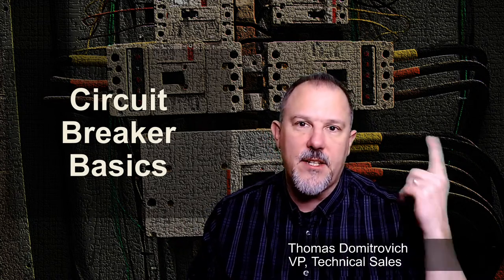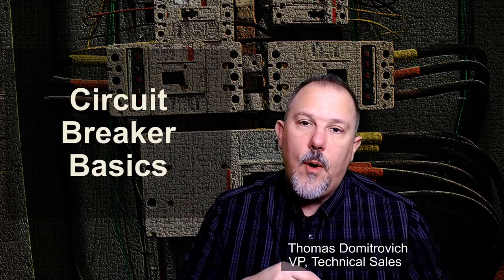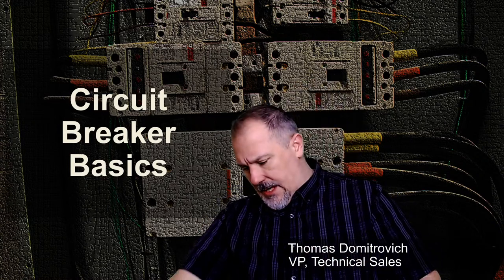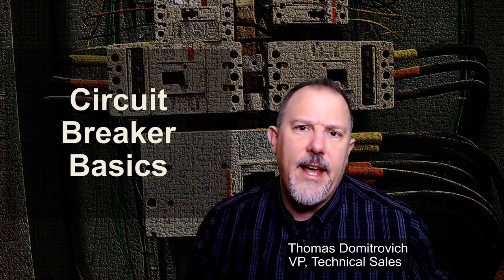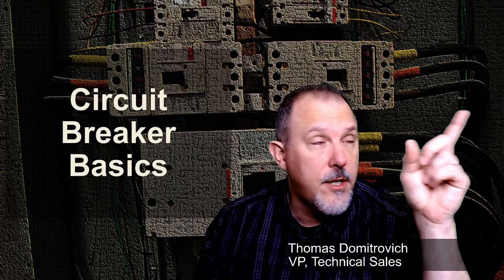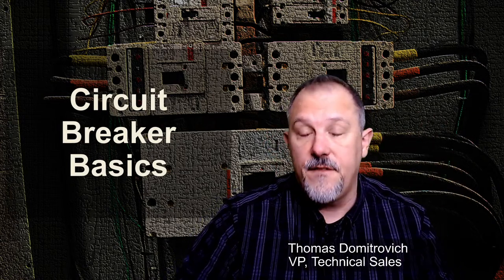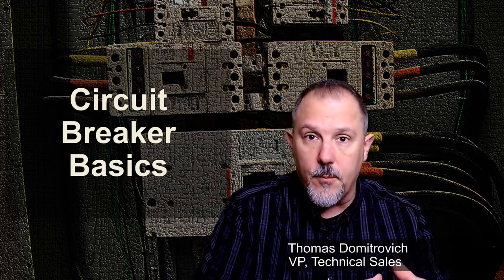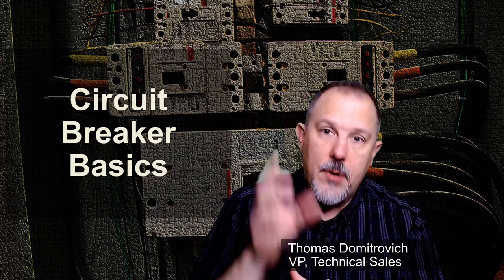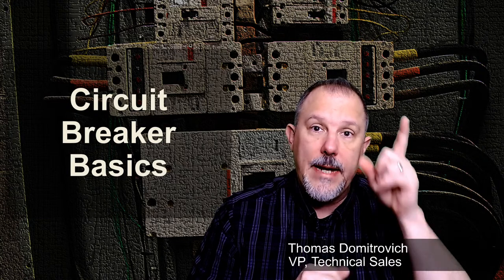I think it was about the same age as when I bought my Harley Davidson. So when I went outside and I was doing something, I changed all my breakers in here to AFGFs. I had one of my breakers tripping on a circuit going to the backyard. Arc fault, ground fault. When I say AFGF, it's an arc fault, ground fault. So it has arc fault protection and ground fault protection built in. So every one of my breakers are that way. And when I put it in, it tripped on a circuit going into the living room.